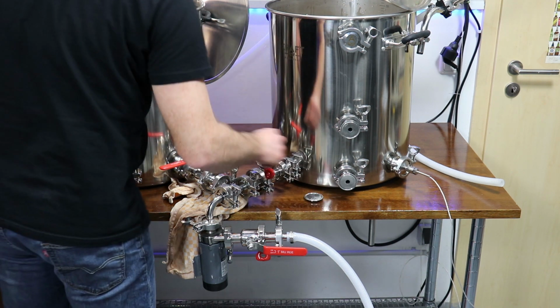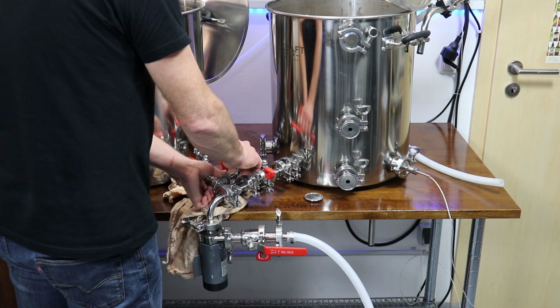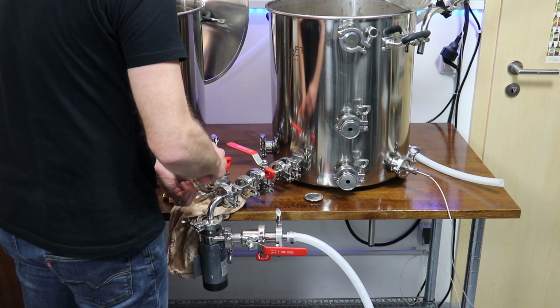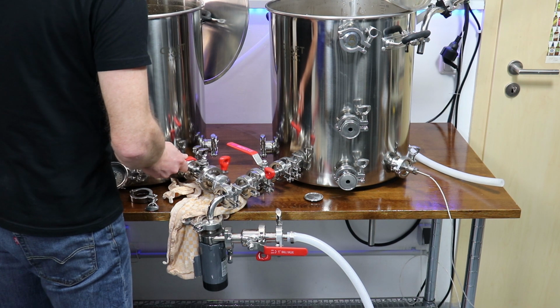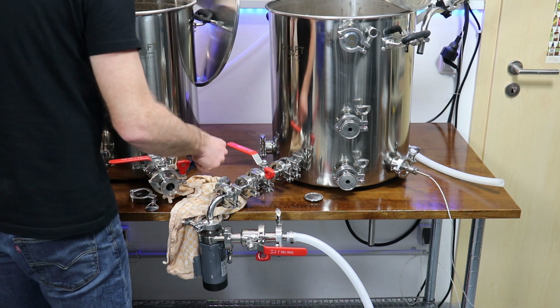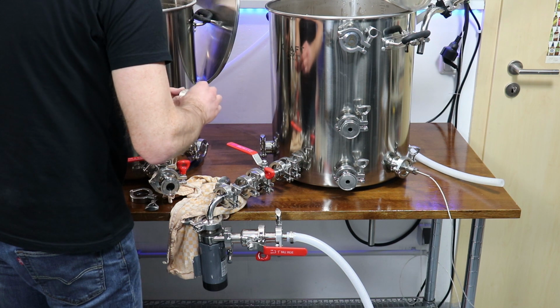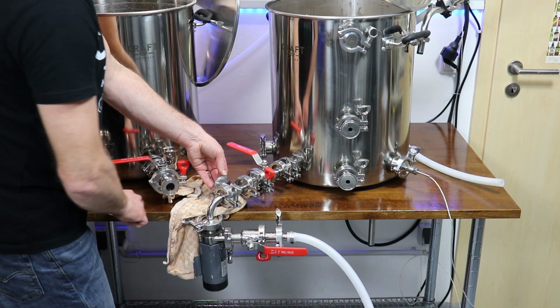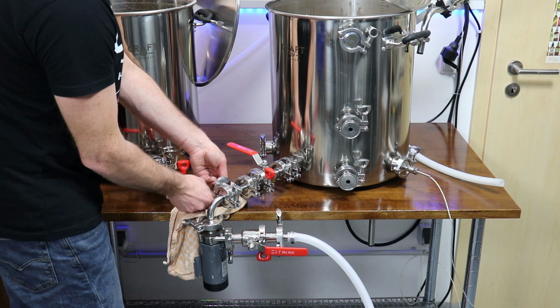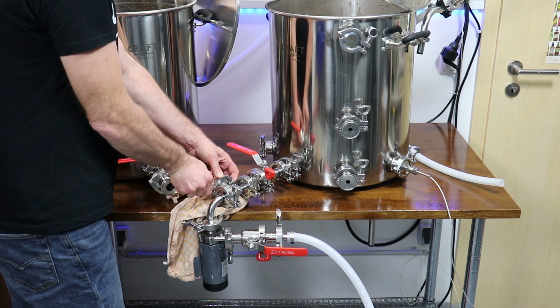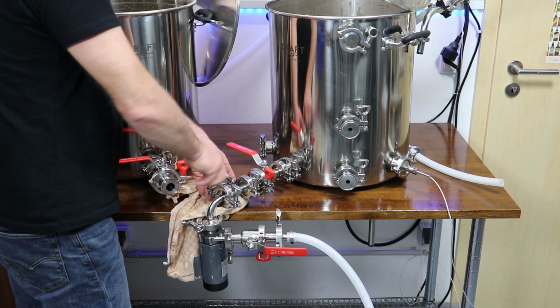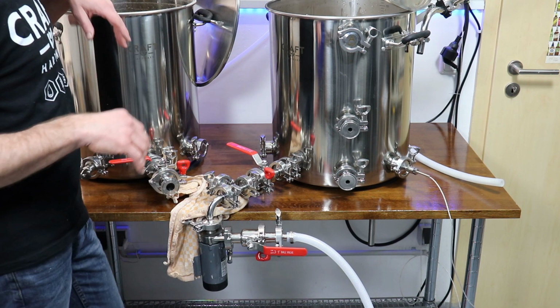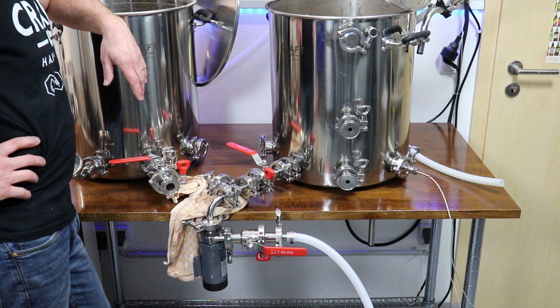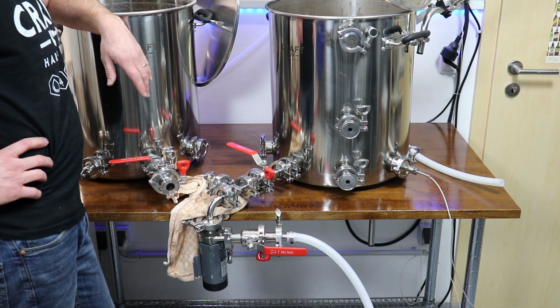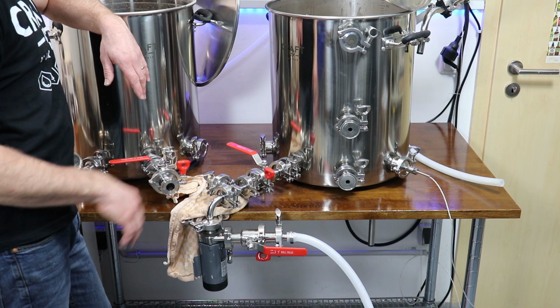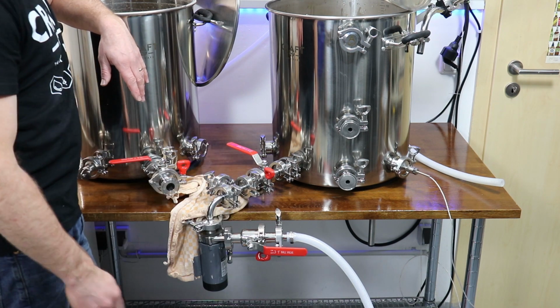All I'm going to do is open this up here—making sure everything is closed, please—and move that away. A couple drops, not much. I'm not overly concerned about sanitation on this line, because what I'm going to do is recirculate very hot water through it—not boiling, of course, but maybe starting at 90 degrees when we begin the cooling process, 93, 94. I'll let that recirculate through, and it will sanitize this entire liquid path.